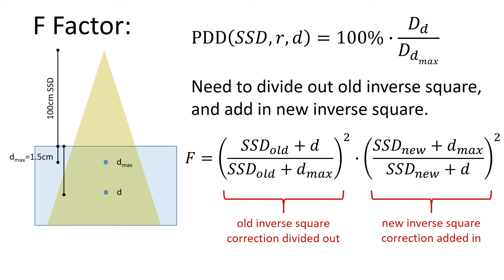So to get the f-factor, we basically just need to divide out the old inverse square that's basically inherent in the PDD, and add in the new inverse square correction. So I've broken it up here based on the old inverse square correction being divided out, and then the new inverse square correction being added in, or multiplied in. And you can see that here with this f-factor, and we can just calculate that directly.